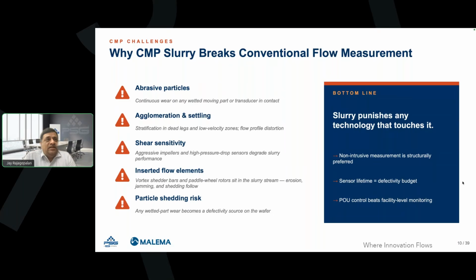Shear sensitivity: if you have any rotating parts in the device or any obstructions, that can create shear, and the softer material around the abrasive particle can come out and cause problems. So generally the vortex flow meter, paddle wheel, or differential pressure type of flow meters or flow controllers should be avoided. And obviously, those products also have particle shedding risks.